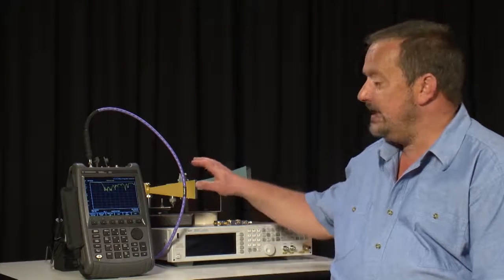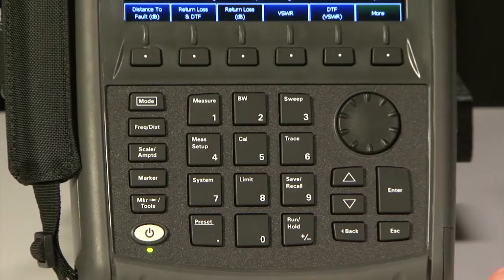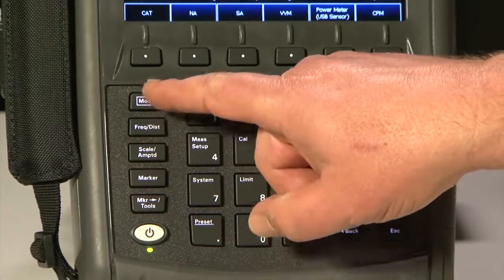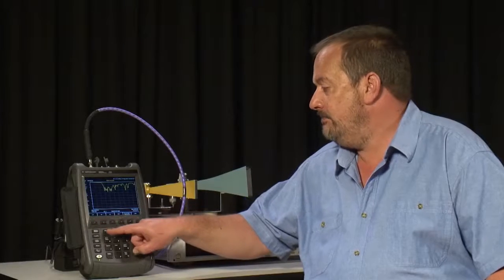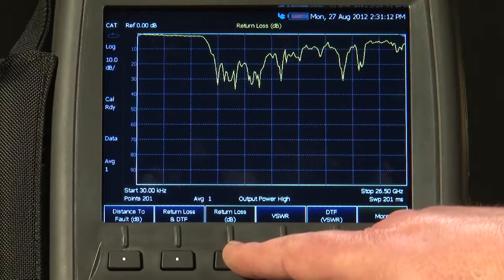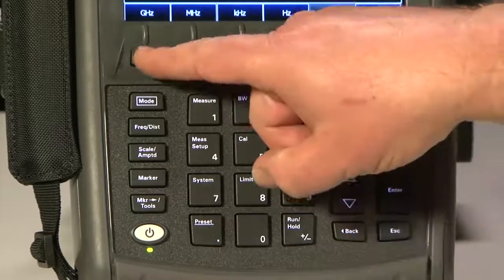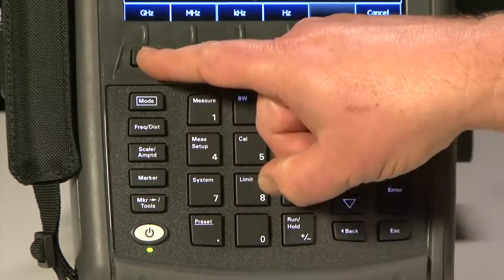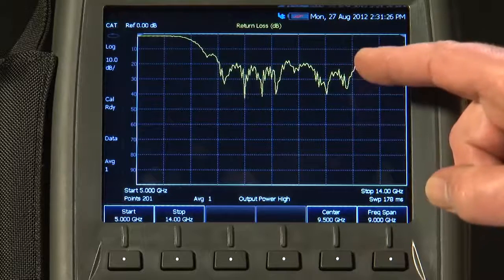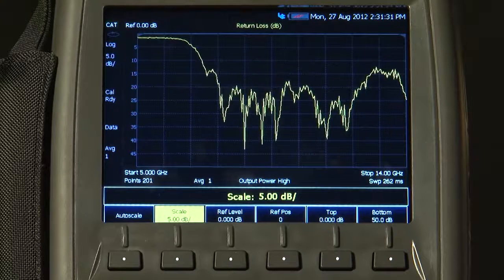Let's start by sweeping this X-band microwave horn antenna with a short test cable as we would in the workshop for acceptance testing prior to going out on site. First, I press MODE, and make sure we have CAT cable and antenna test selected. Then I will press measure, and we have return loss selected. So I will just set a start frequency of 5 GHz, and perhaps a stop frequency of 14 GHz. And you can see we are sweeping the return loss of the antenna. I will just change the scale to 5 dB per division so we can see it a bit more clearly.